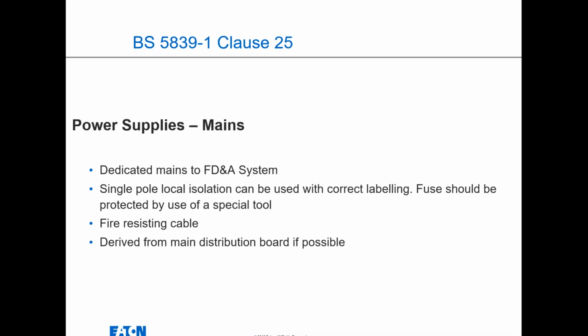Power supplies, as I touched on earlier: it's got to be dedicated mains to the fire alarm, single pole isolation, and a fused spur. Fire resistant cable must be used, and it should be derived from the main distribution board if possible. If not, it might have to be put down as a variation.